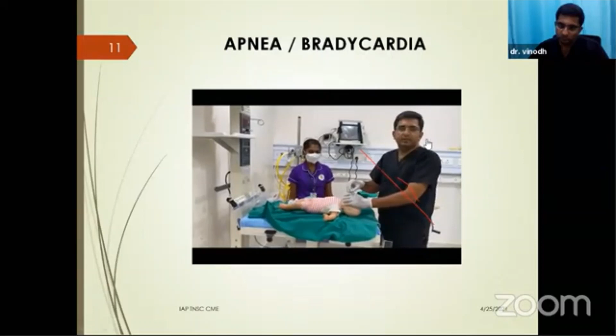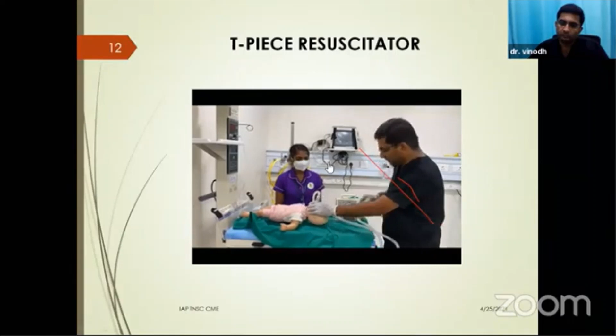A few words about the T-piece resuscitator. I just wanted to show the T-piece resuscitator. It's an alternate way of giving positive pressure ventilation. This is the gas inlet where we are supposed to give the inlet of gas. We can give a flow of 5 to 15 liters per minute. This is the outlet, and this tubing has to be connected, and the mask has to be placed over the baby's mouth and nose. This is the outlet valve. This one is the inlet for the gas.